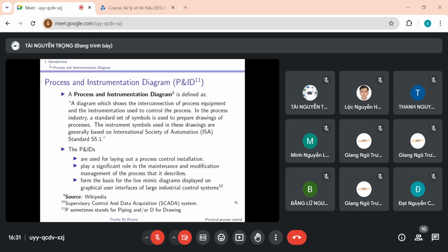In the process industry, a standard set of symbols, and we'll talk about that later, is used to prepare drawings of processes. The instrument symbols used in these drawings are generally based on the ISA standard S5.1. ISA stands for International Society of Automation. The P&IDs are used for laying out a process control installation, so they're very important in the design phase. They play a significant role in the maintenance and modification management of the process, but also of the controller structure that it describes.